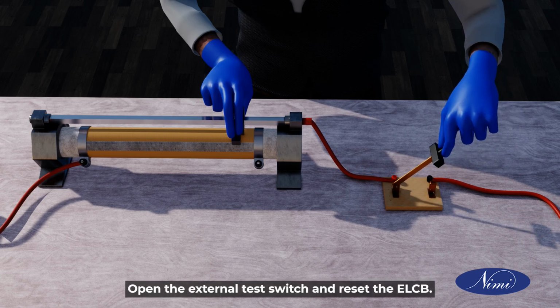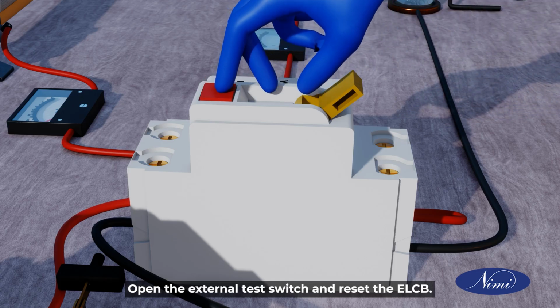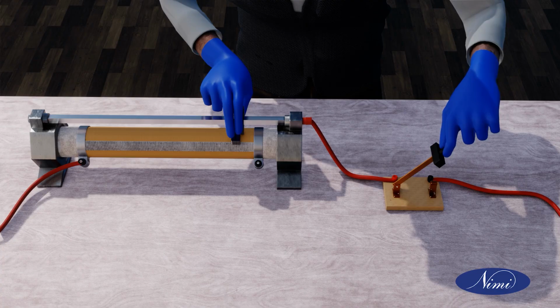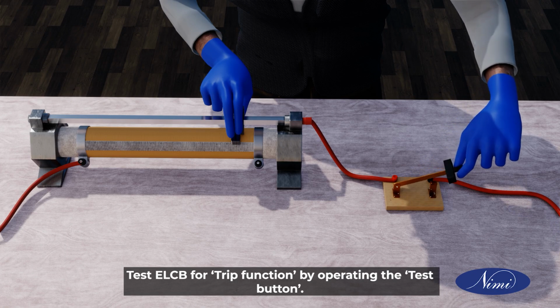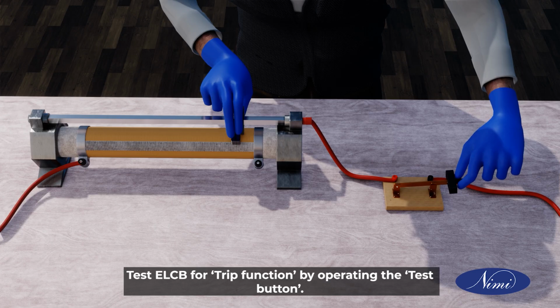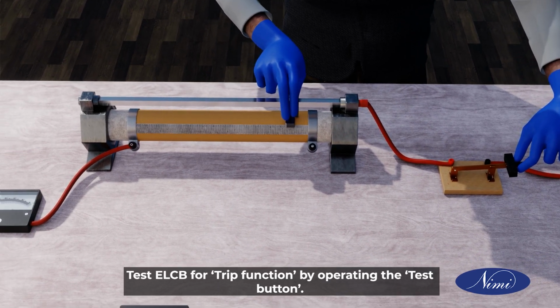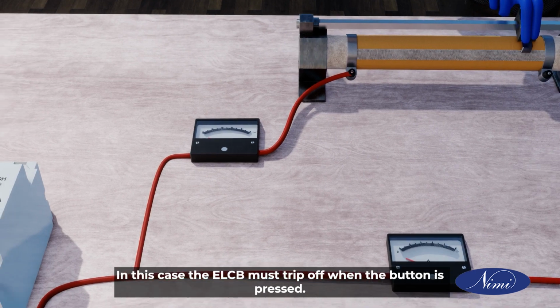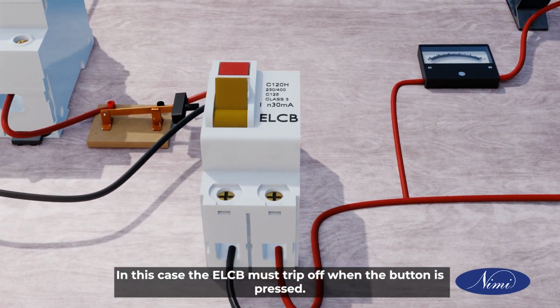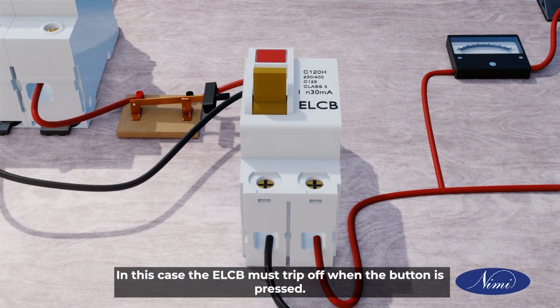Open the external test switch and reset the ELCB. Test ELCB for trip function by operating the test button. In this case, the ELCB must trip off when the button is pressed.